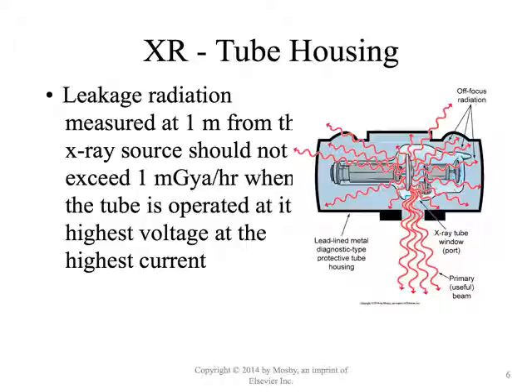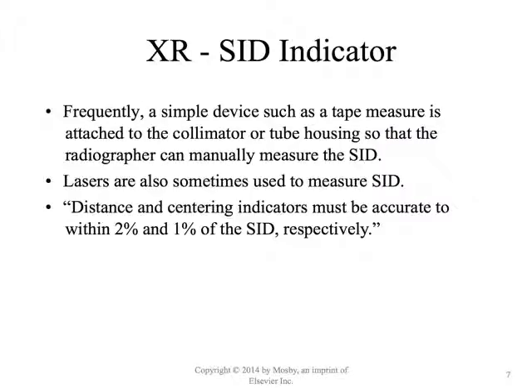Now, they're not going to make an hour-long exposure with your X-ray equipment. The physicist will come in and make an exposure of some predetermined length, like 20 seconds, and then they'll extrapolate that out to an hour, right? They'll measure the leakage at a shorter exposure and then just lengthen that time out. But we've talked about how when we produce X-rays, they're produced isotropically in all directions, so we need to shield from any off-focus radiation. For X-ray, we will also have an SID indicator.